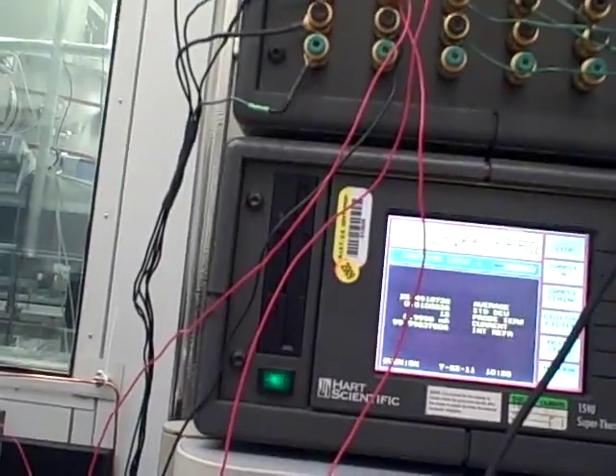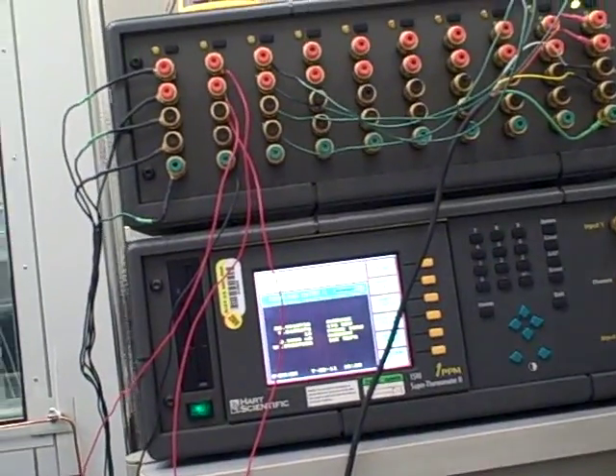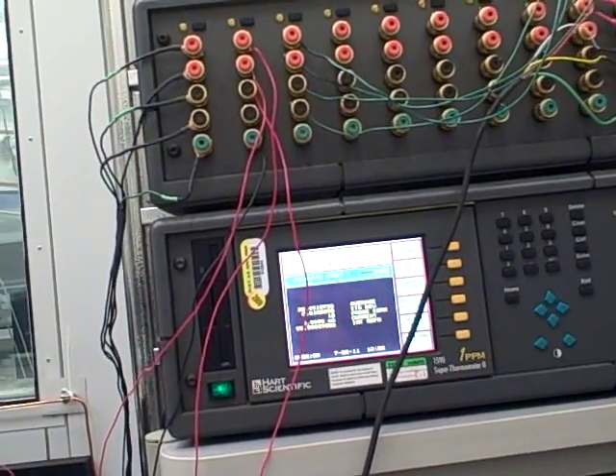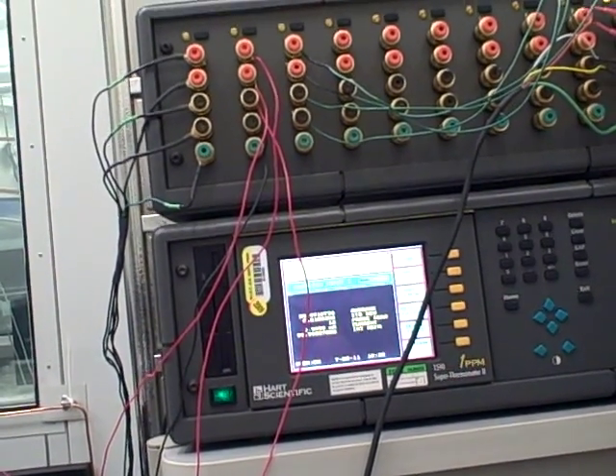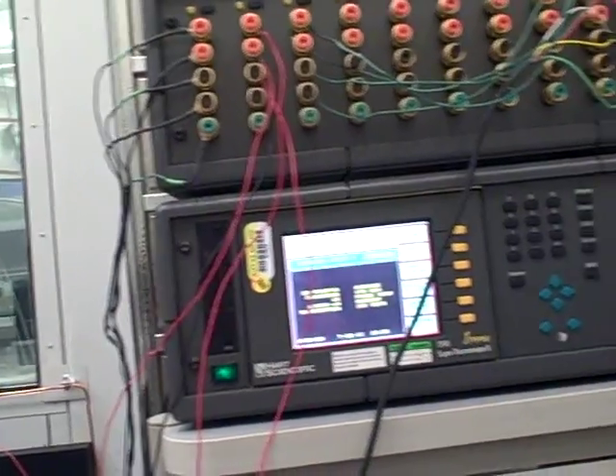Oh my goodness, look at all these wires. So this probe is connected to this? Yes, which is connected to this. This is a multiplexer, so you can put up to 10 different probes into this instrument, and you can select them by just pressing these buttons. So it's a very versatile instrument. That's one of the things that I do here: I calibrate thermometers for use in the group.